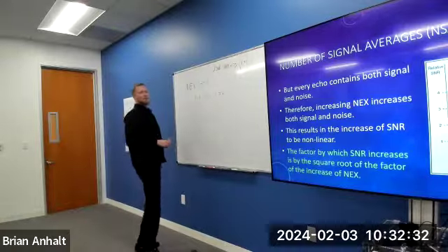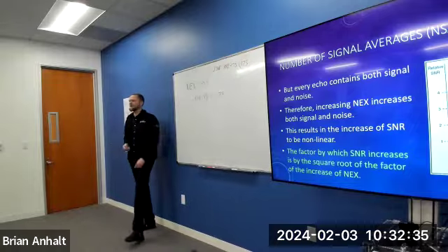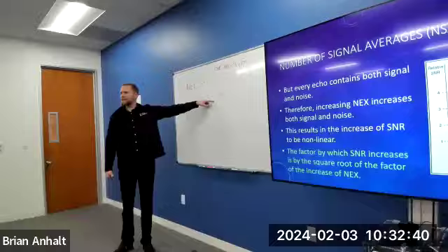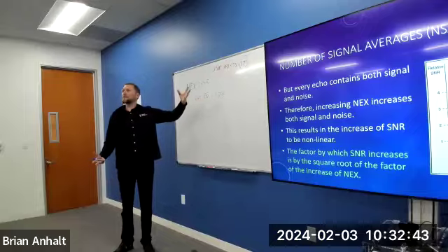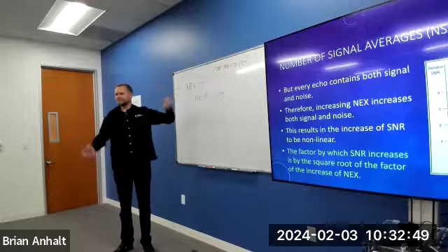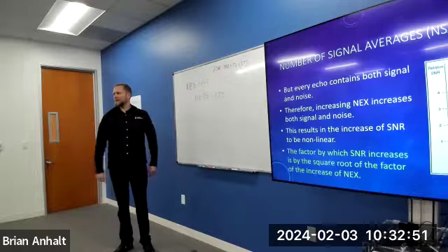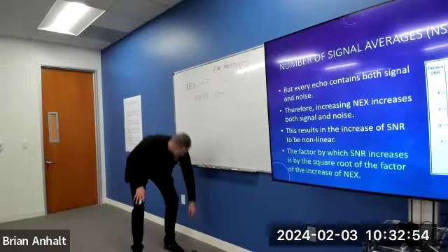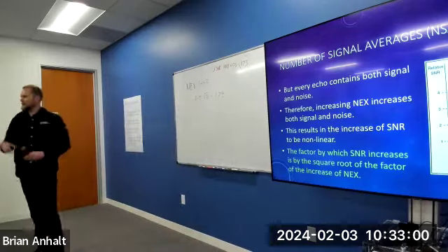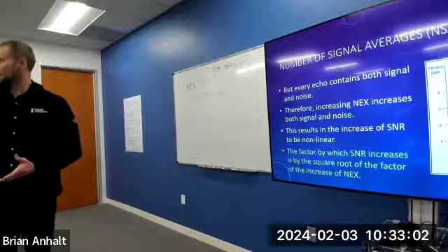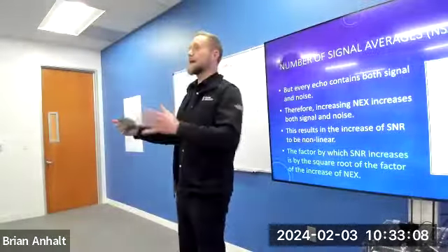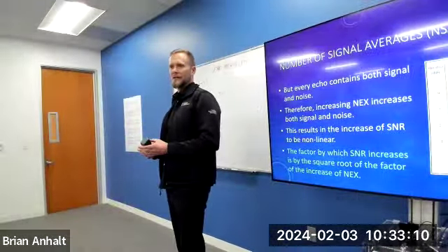It is, because my scan time equation is TR times NEX times something called the phase matrix. So in this case, I've got 73% more SNR, but what have I done to my scan time? Tripled it, right? 3 times the scan time for 73% more signal. Is that efficient? Maybe, maybe not. So write that down in your little triangle. Increasing NEX increases our SNR by the square root of the factor of increase. But it also directly increases my scan time linearly, right?